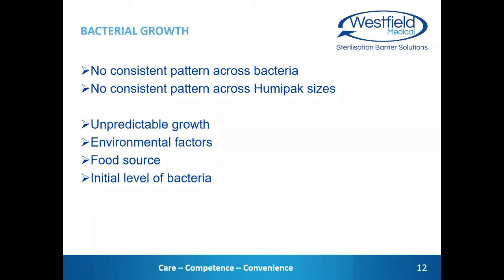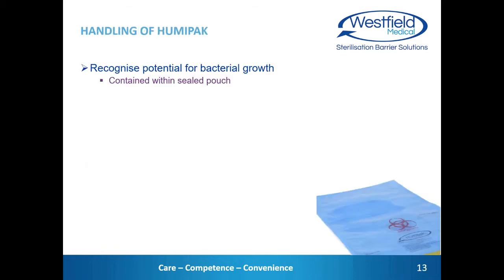The other point to note really is that other alternative options such as sprays and gels are designed to keep instruments moist, but they don't kill bacteria either. Even enzymatic sprays, they will start to break down the proteins, but the bacteria are still there. It's not a different product with HUMIPAK. So, yes, we recognise that there's potential bacterial growth, but it's contained. And we believe that on a risk basis, it's better to ensure containment of infectious material than it is to potentially disperse bacteria through the transit route. The pack is then only opened once it's in the controlled environment of the decontamination area.